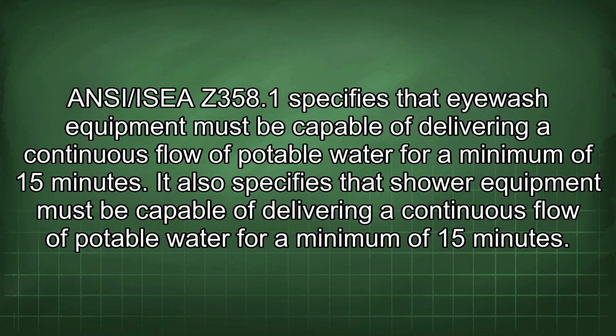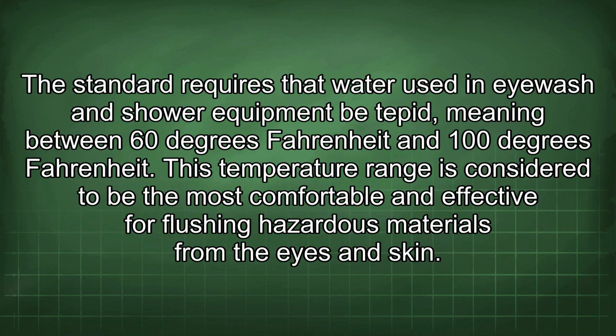ANSI/ISEA Z358.1 specifies that eyewash equipment must be capable of delivering a continuous flow of potable water for a minimum of 15 minutes. It also specifies that shower equipment must be capable of delivering a continuous flow of potable water for a minimum of 15 minutes. The standard requires that water used in eyewash and shower equipment be tepid, meaning between 60 degrees Fahrenheit and 100 degrees Fahrenheit. This temperature range is considered to be the most comfortable and effective for flushing hazardous materials from the eyes and skin.